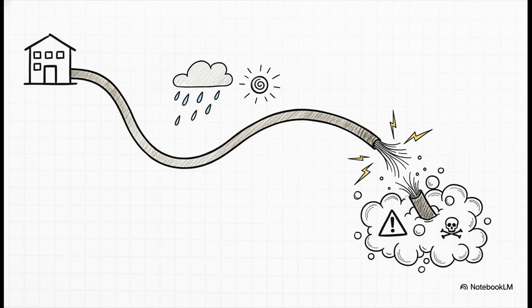Imagine a high-voltage power line leaving a nice, safe switch room, crossing a harsh, weather-beaten open deck, and then dropping straight down into a highly volatile Zone 1 pump room. That cable is going to face mechanical stress, chemical exposure, wild temperature swings, the whole shebang. If it's not perfectly specified for that exact hazardous environment, it literally becomes a conduit for disaster.